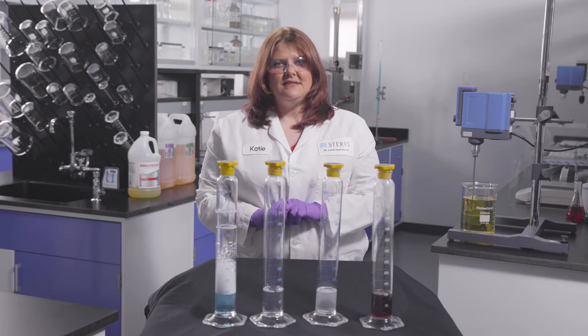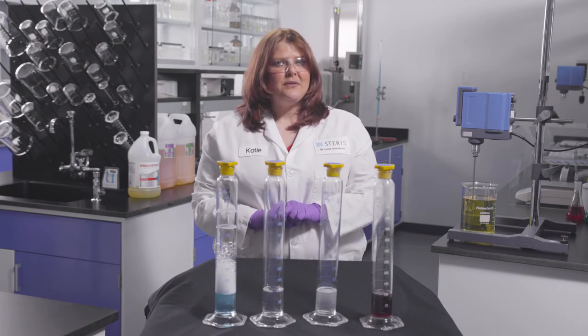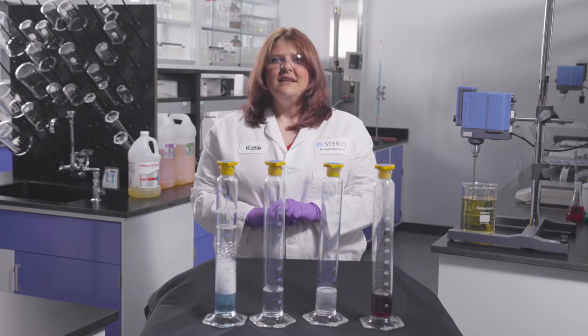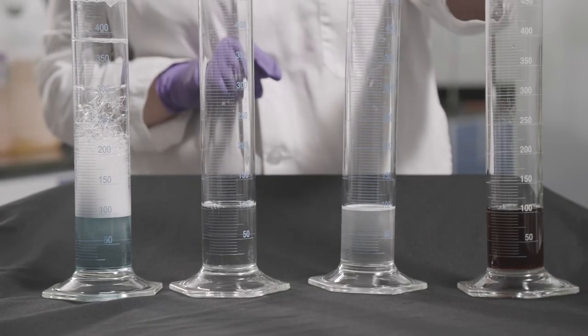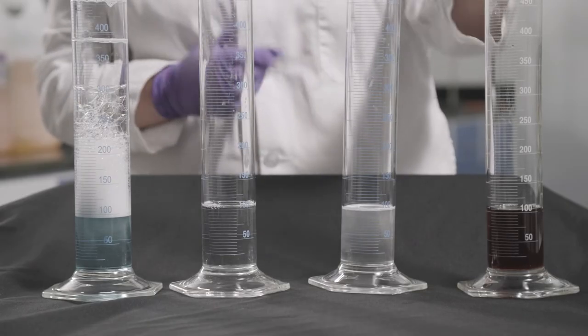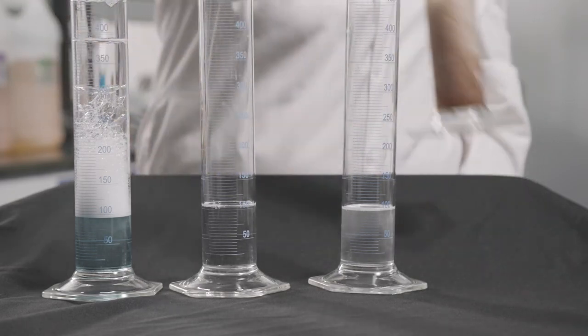When you clean medical devices, the proteins and surgical soils create foam. What's unique about the Prolystica high performance chemistries is that it also de-foams the soils while cleaning. To show you just how foamy protein soils can be, here is another cylinder with only water and protein blood added. You can see as I agitate the solution, protein creates foam.